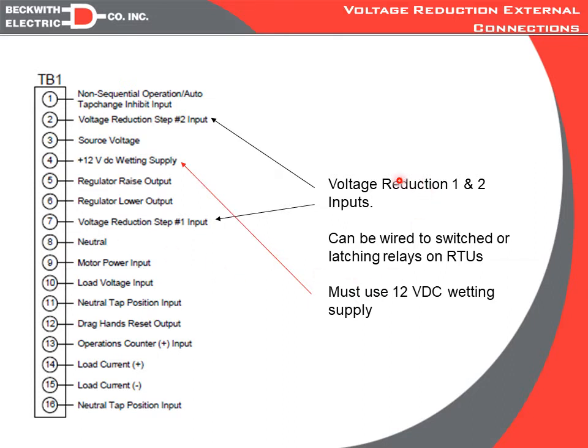A second hardware way would be the two voltage reduction inputs we had talked about. So on TB12 we have input number 2, and then down on TB17 we have input number 1. Now both of these would have to be wetted, so they're contacts wetted with our 12 volt power supply, which would be off of TB14. So if we ran TB14 to one side of two contacts on an RTU and brought the other sides back to TB17 and TB12, we could then issue latching commands to those outputs on the RTU and have the RTU drive reduction that way. So if we have an older legacy RTU that cannot support polling the control directly via DNP, we can do a hardwire approach using those two external contacts.